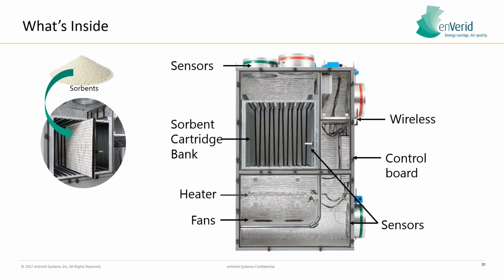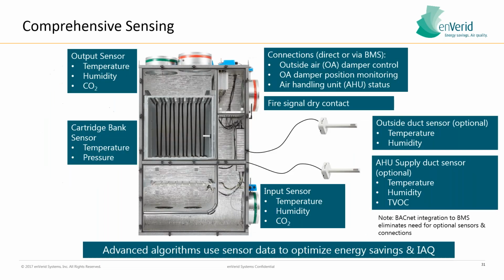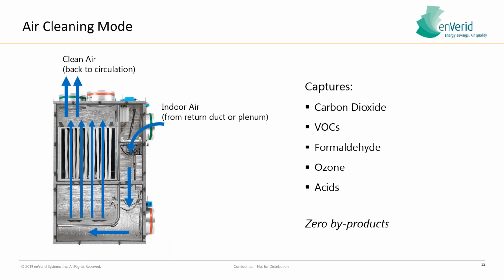We don't want this to be a black box, so we have BACnet integration. So there's a controls board there, so we can connect with the BMS. And then we have sensors within the unit measuring CO2, formaldehyde, total VOCs, which would include formaldehyde, temperature, pressure, humidity, and then we have a total VOC sensor in the space. So you can see the input sensor, temperature, pressure, humidity, and CO2 at the input and the output, and then the VOC sensor within the space as well. All this information is broadcast using essentially a wireless signal, the 3G, 4G connection.